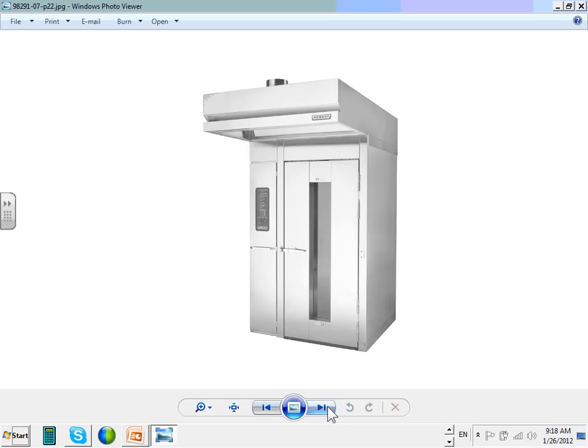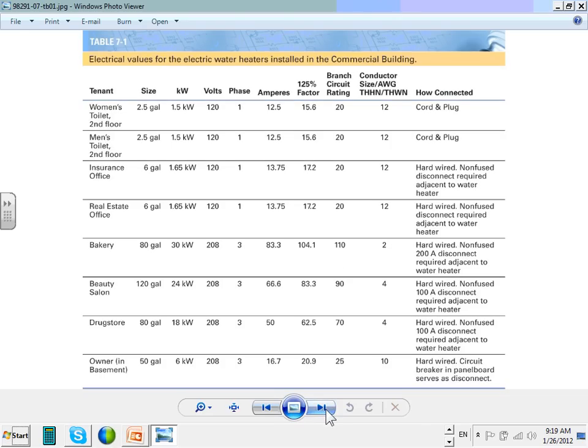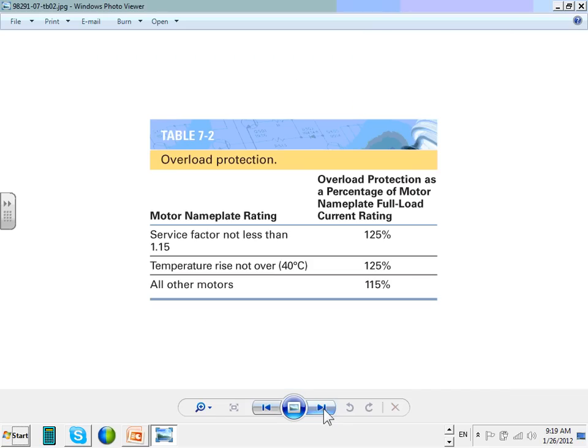So a lot of these guys, okay, so the rest of them, they're taking examples of the loads that we have in the book. I know for a fact that we took, this is sizing. Basically what they're doing is they're sizing branch circuits. And we told you guys before, when you size a branch circuit, for a continuous load it's 1.25 times the load, we size the overcurrent protection device as well as the conductor. And these are the examples that we do.